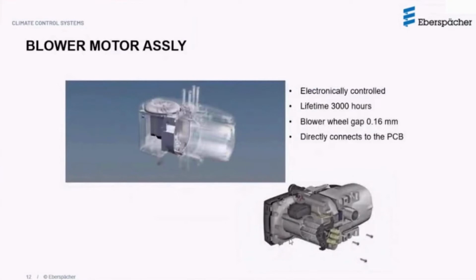The fan assembly itself, as you can see, is an EC motor. It has a lifetime of 3,000 hours, again depending on the variant, whether it's 12 or 24 volt. Officially, you can achieve up to 5,000 hours. A couple of things have also changed in the design, such as the gap between the blower wheel and the machined surface, which is a very important gap to be maintained.